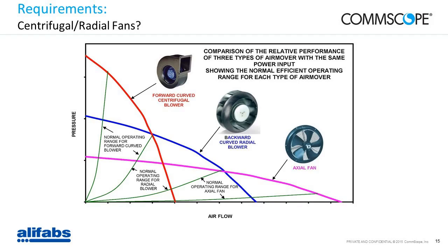And we've opted for the one in the middle, the backward curved radial fan. The reason is that it's the perfect balance between good resistance against pressure, and good airflow, good cooling capacity. If you look at an axial fan, which some of you may have on your sites as backup fans operating on 48 volt DC, many of them get blocked very quickly. They've got a fantastic airflow on day one, but as we add more restrictions, the airflow very quickly diminishes. The opposite goes for a forward curved centrifugal fan, where you get pretty low airflow, but you'll be able to fight against a lot more restriction. So really, starting with the basics is a backward curved centrifugal fan.